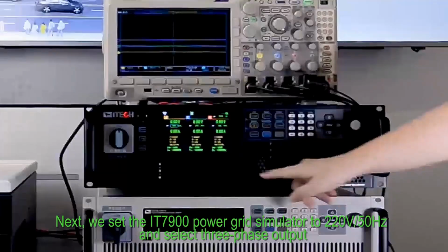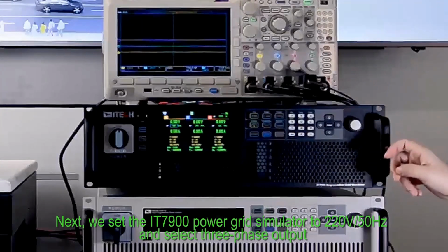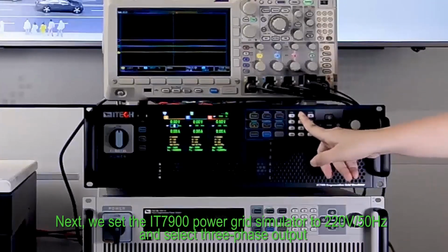Next, we set the IT7900 power grid simulator to 220V, 50 Hz and select 3-phase output. Start the output of the grid simulator, provide a voltage signal to the AC terminal of the PV inverter, then start the inverter.